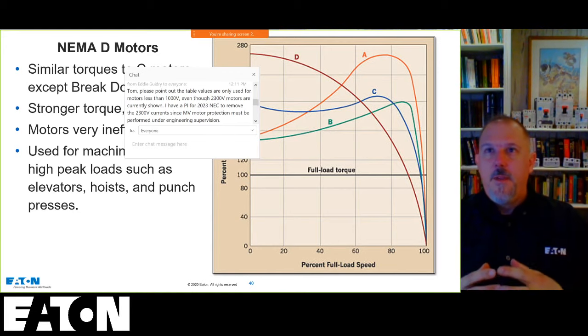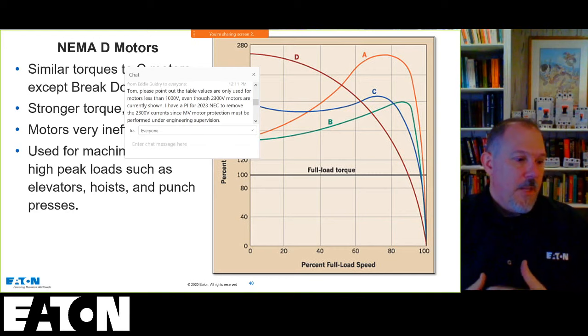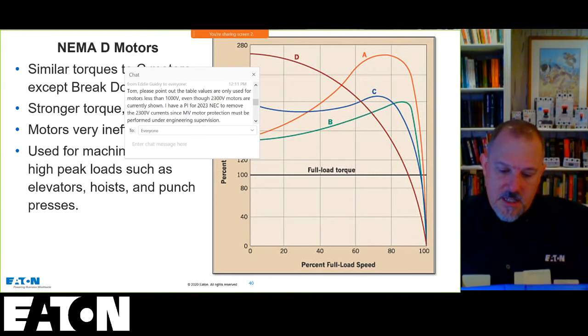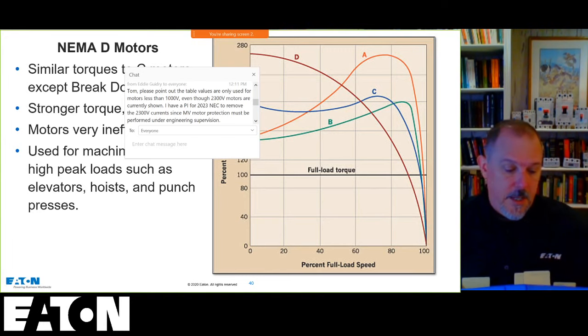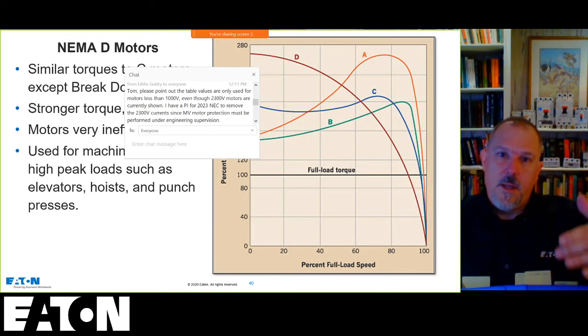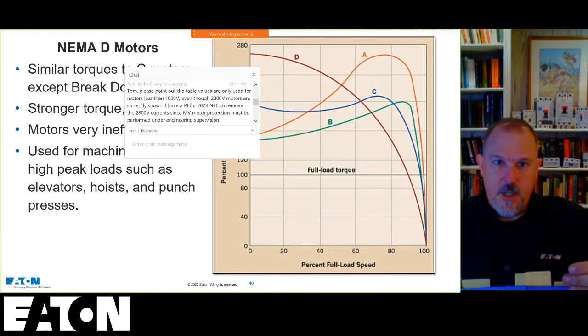From a National Electrical Code perspective, it's really important when you're thumbing through the NEC, when you're looking at either a table or a section, to look at what part it is in. For example, 430.52. To point out the table values, I'm just looking at 430.52 because that's where it's open, but it's in Part IV, Motor Branch-Circuit and Ground-Fault Circuit Protection. It's good to read the very first section in each part, which will typically give you any of the general requirements or general information. And a lot of times, things like what Eddie is pointing out, whether it's 1,000 volts and below or whatnot, is in that first section of the code.